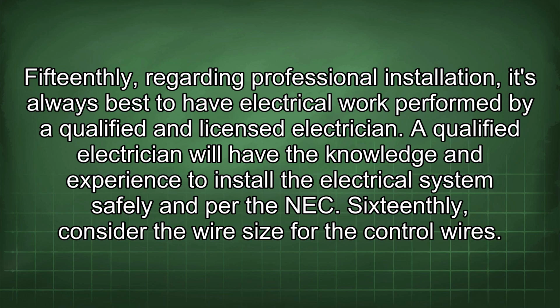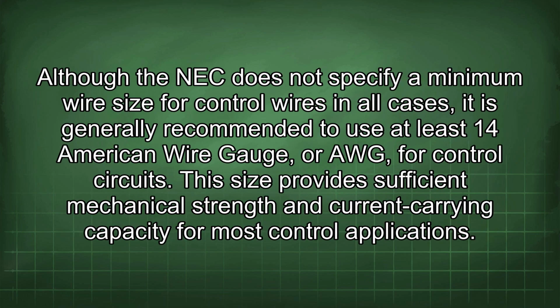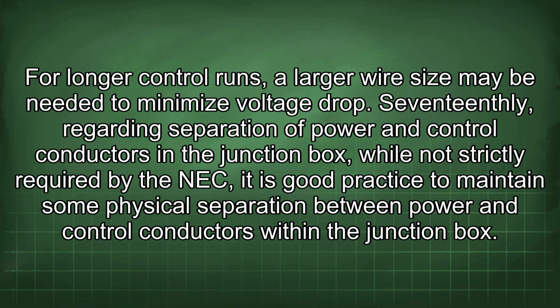16thly, consider the wire size for the control wires. Although the NEC does not specify minimum wire size for control wires in all cases, it is generally recommended to use at least 14 American wire gauge for control circuits. This size provides sufficient mechanical strength and current carrying capacity for most control applications. For longer control runs, a larger wire size may be needed to minimize voltage drop.